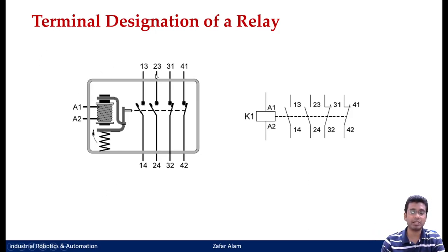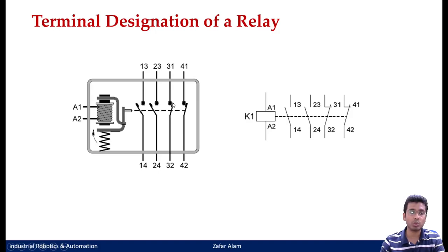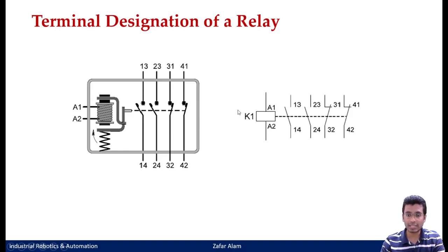Finally, a relay can make or break a contact — you can have multiple contacts in a relay. Once the electromagnet is energized, it pulls this strip made of ferromagnetic material and in doing so, whatever circuits are open will close, and whatever circuits are closed will open. So relay K1 in an electrical circuit diagram would be represented in this way — a relay can have multiple contacts. This is one relay and this is an open contact of the same relay K1.